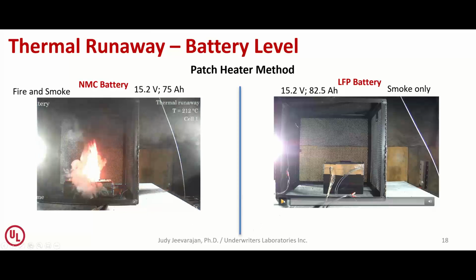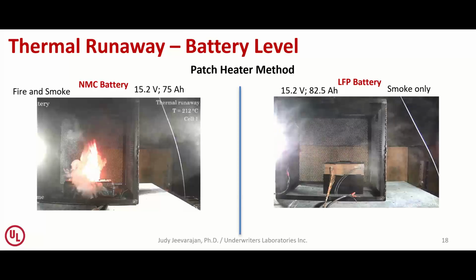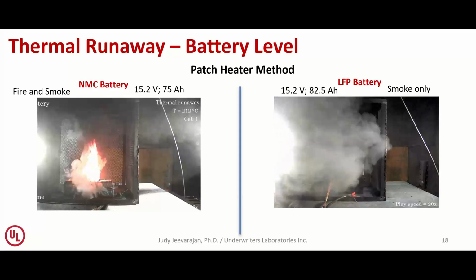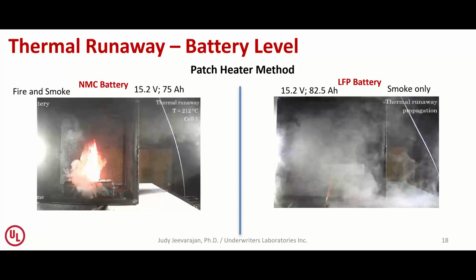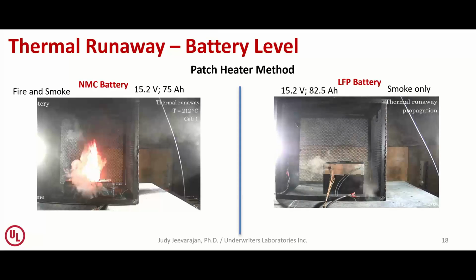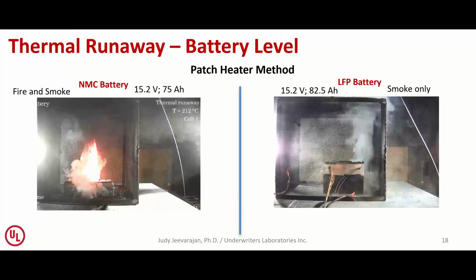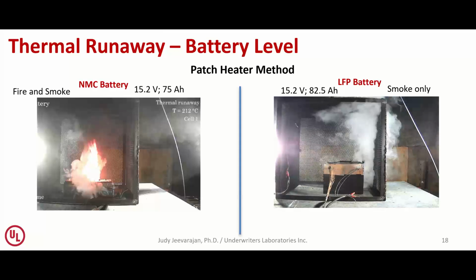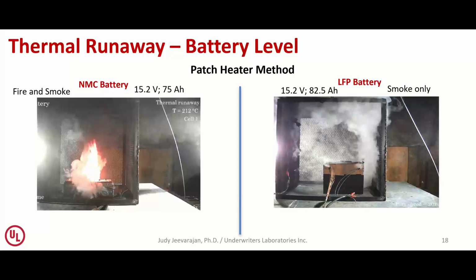You can see that had a very big fire. In the case of the LFP, we actually had to use about 8 heaters on the cells to cause this to go into thermal runaway. The design of the battery is such that if only one cell is heated up, it goes into thermal runaway, but it doesn't propagate to the other cells. What we wanted to do was a worst case test to find out how it behaves under a worst case condition, so we had about 8 heaters to make sure the fire actually propagated.